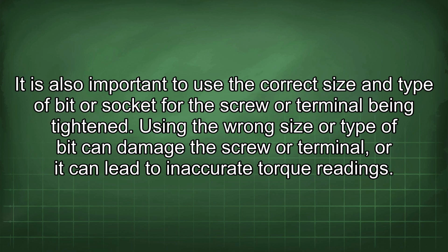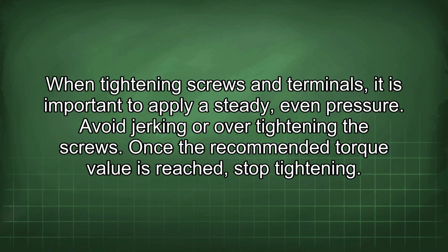being tightened. Using the wrong size or type of bit can damage the screw or terminal, or it can lead to inaccurate torque readings. When tightening screws and terminals, it is important to apply a steady, even pressure. Avoid jerking or over-tightening the screws. Once the recommended torque value is reached, stop tightening.